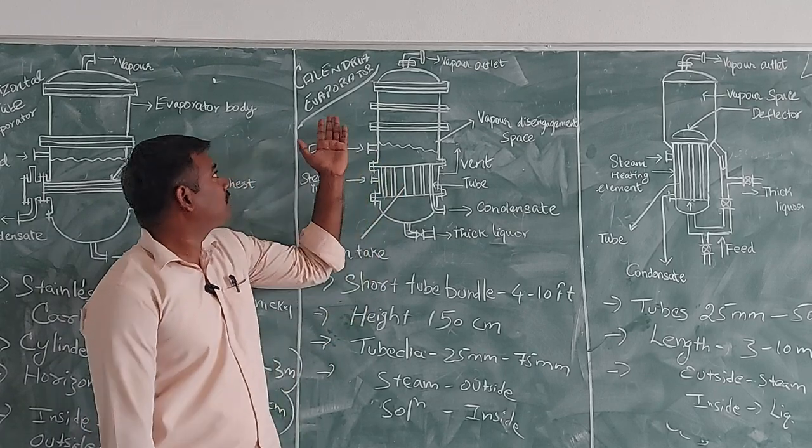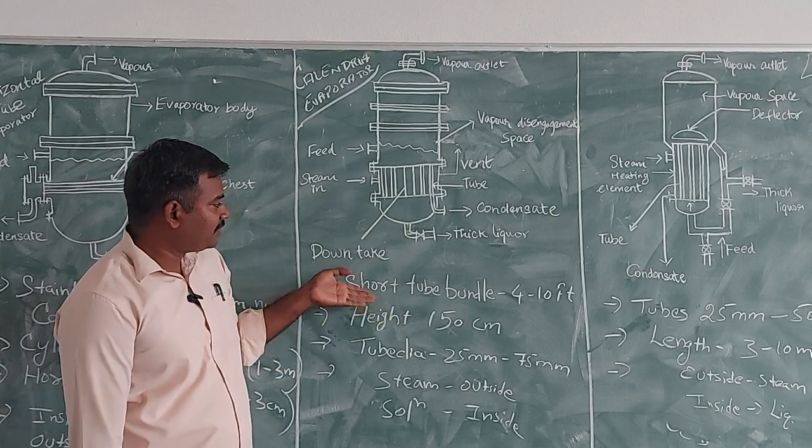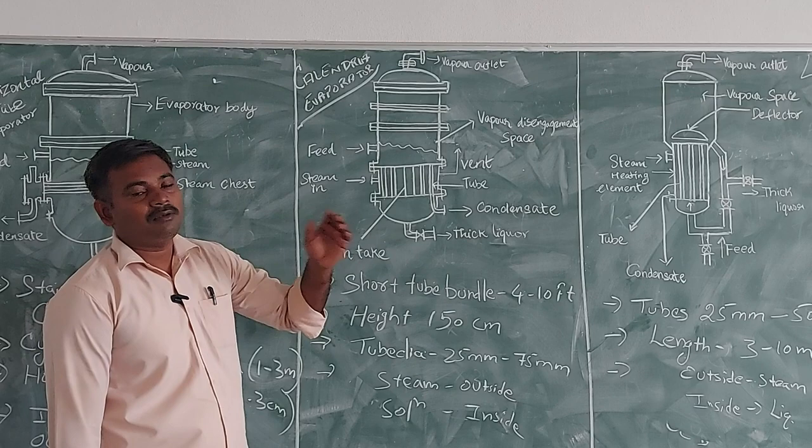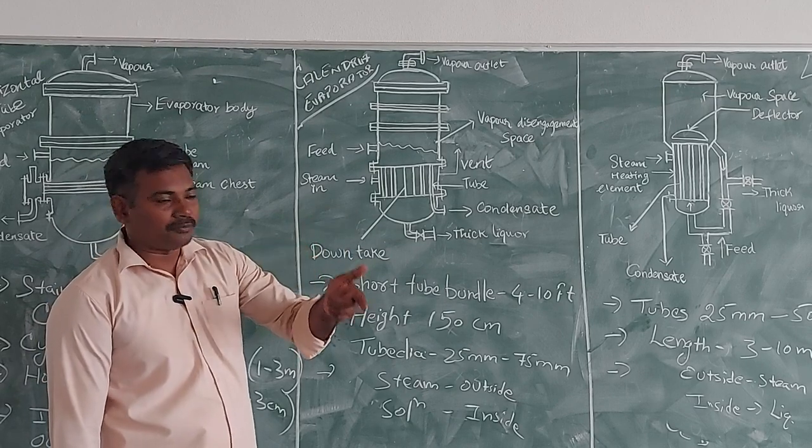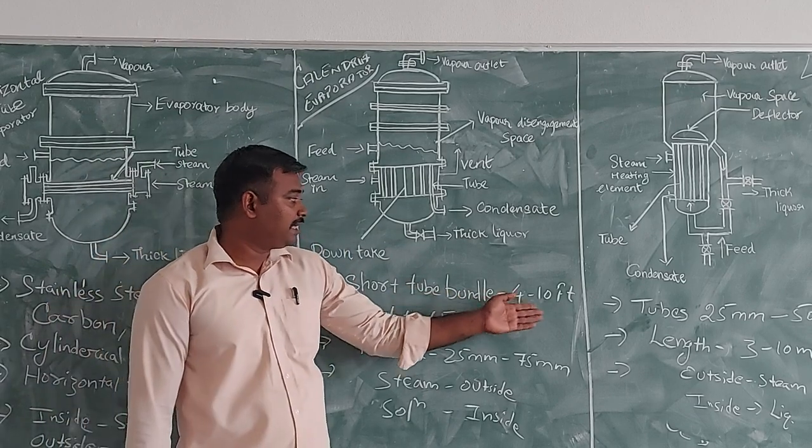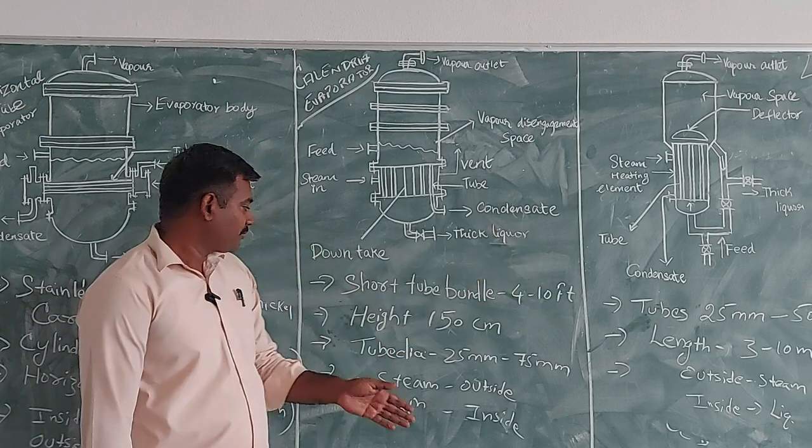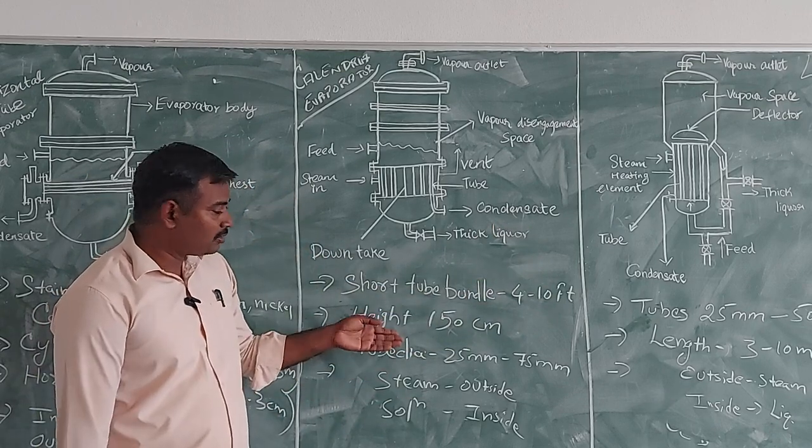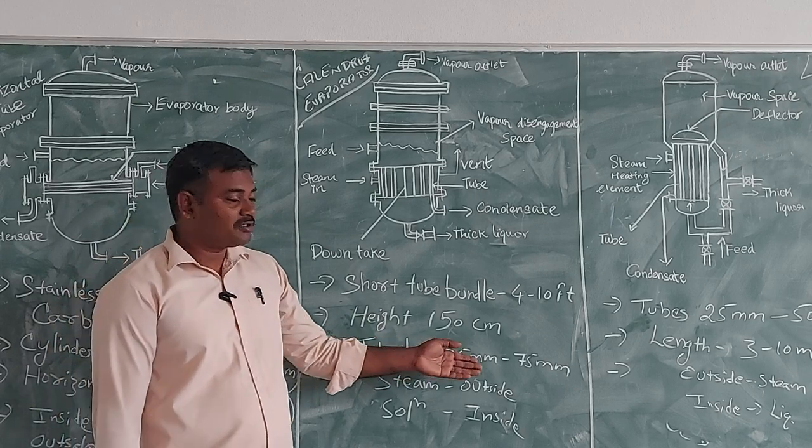So the constructions of your Calandria Evaporator will be, it will be having a short tube bundle itself. So tube bundle indicates the bundle which consists of the number of tubes. So which will be having the height length of 4 to 10 feet. And the height will be 150 centimeter of each tube. Then tube diameter will be 25 mm to 75 mm.